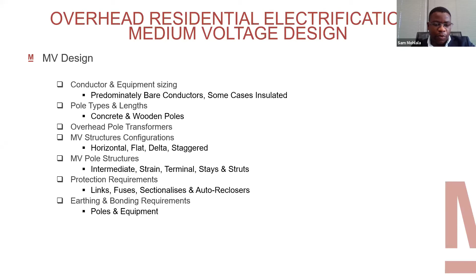There are a few things you can do in terms of earthing for your poles and transformer equipment. Normally on transformer equipment, you can earth your MV and LV together, but that can only be done if your overall resistance to earth is below 1 ohm. However, the normal practice is to earth your MV and LV separately from each other.